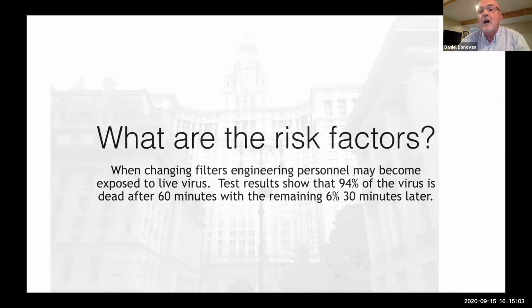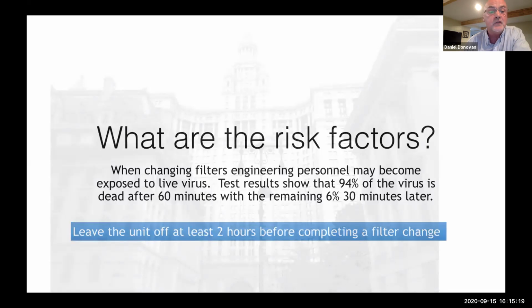Test results from that independent lab show that 94% of the virus is dead after 60 minutes, and the remaining 6% approximately another 30 minutes. So our protocol now is you're going to leave the unit off for at least 2 hours. What we'll do is leave the unit off overnight and then come back in the next day, and then you do your filter change. But still, you wear all your PPE. You never do anything without proper PPE, especially in this COVID world that we're living in.